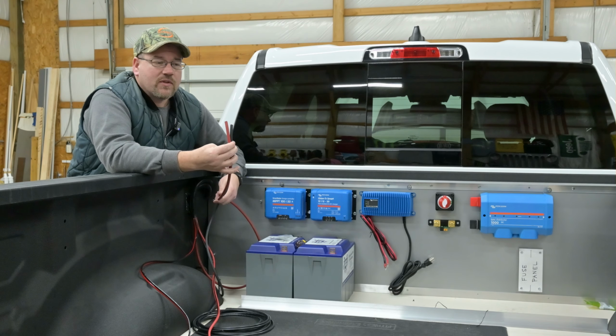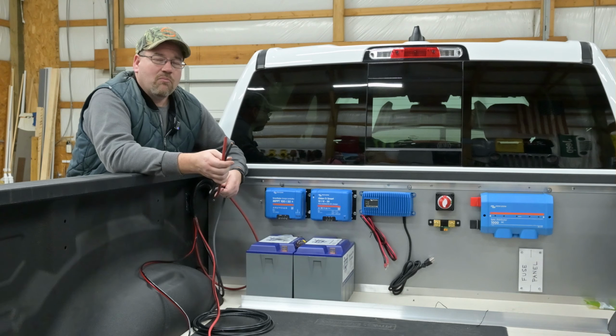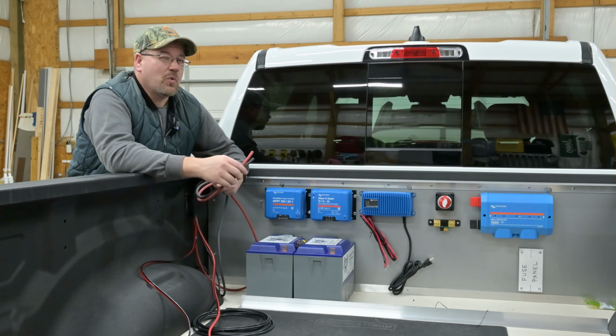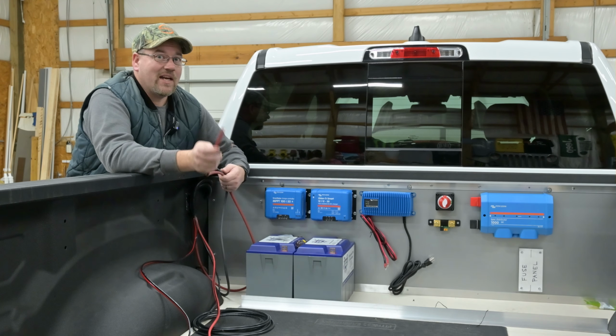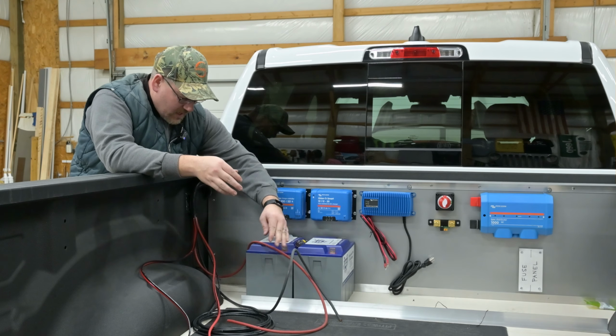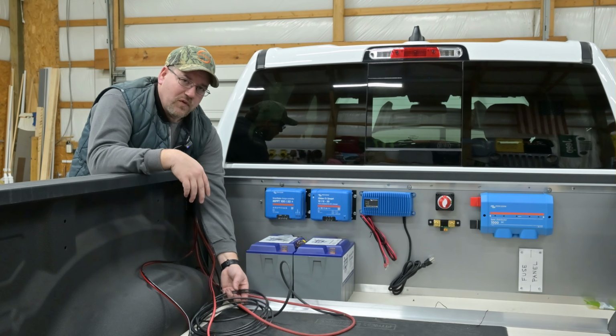For 30 amps, 6 gauge seems like a lot, but taking into account the 15 to 20 feet of cable run I'm going to have, it's actually just the right size. Another cable down here is just a physical ground.